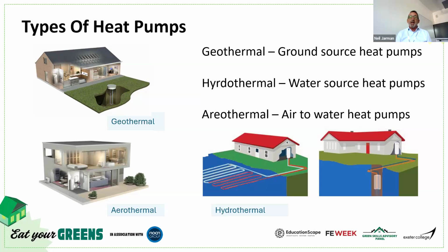Now, with the geothermal and the hydrothermal ranges, you can bore down, or you can have an array of pipework in the ground or in the water, as detailed in the drawings there. So the geothermal looks very much like the hydrothermal array of pipework. You obviously need a lot of land, and the capex on the geothermal is high in comparison to the hydrothermal, and the hydrothermal again is slightly more expensive than the air to water heat pumps, the aerothermal.